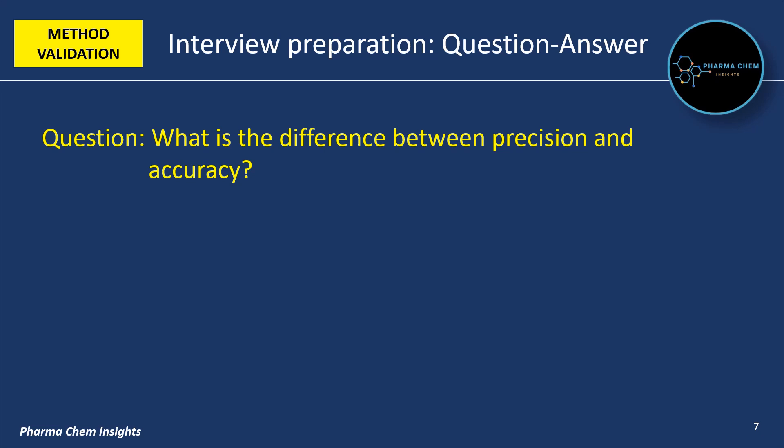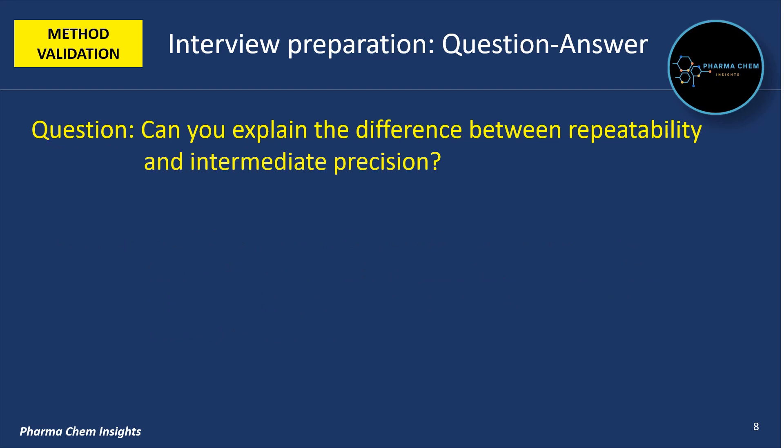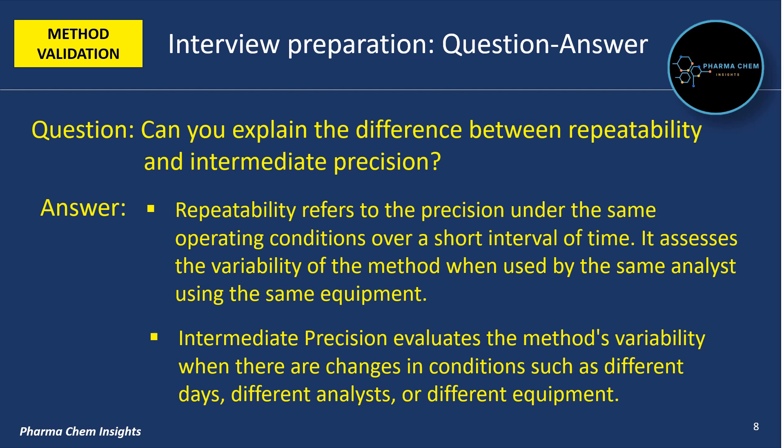What is the difference between precision and accuracy? Precision refers to the consistency of results when the method is repeated under the same conditions, while accuracy refers to how close the test results are to the true value. Next: can you explain the difference between repeatability and intermediate precision? Repeatability refers to the precision under the same operating conditions over a short interval of time, assessing variability when used by the same analyst under the same equipment, while intermediate precision evaluates the method's variability when there are changes in conditions such as different analysts or different equipment.